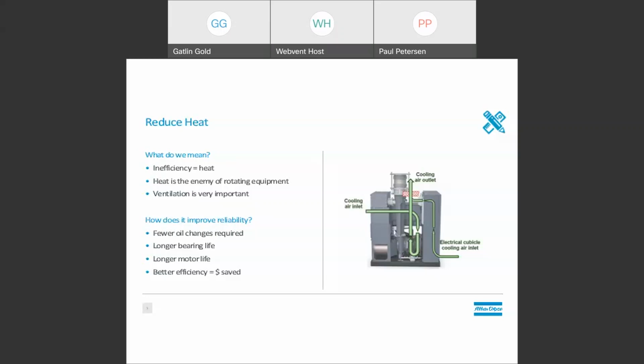Heat is even more critical in non-contact bearing applications like high-speed turbos. Most turbos use permanent magnet motors. The magnets within the motor windings will degrade over time with prolonged exposure to high heat. Manufacturers of lower cost turbos use process air to cool the motor before compression. This preheats the air before entering the blower and motor. This results in lower efficiency and can cause premature failure due to that excess heat. It also exposes sensitive airfoil bearings to high heat that can lead to deformation of their very precise geometry, which again could result in premature failure of that bearing and blower.